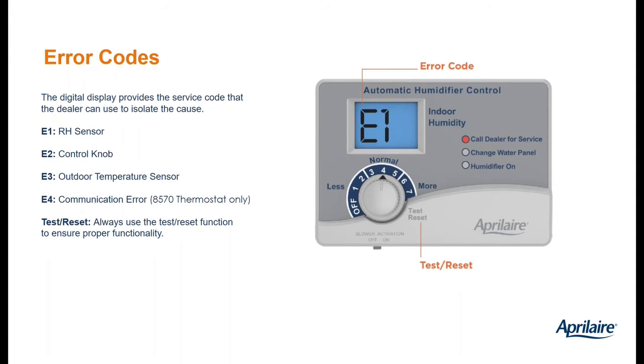E1 is the unit saying there's a problem with the relative humidity sensor. What do you do? Turn the dial to test/reset. And you can tell the consumer right over the phone to do this. Turn the knob to test/reset. After a couple seconds, it'll reset that error code. Have them turn it back to whatever number it was set to previously, and see if the error code goes away. If it does, then it was just a power surge or a brownout or something like that. Just like rebooting your computer or rebooting your Roku box, rebooting your Wi-Fi router, something you'd have to do on a regular basis. Doesn't mean the humidistat's bad, because you're going to turn it to test/reset and see if the error code goes away. If it comes back, then of course replace the humidistat.